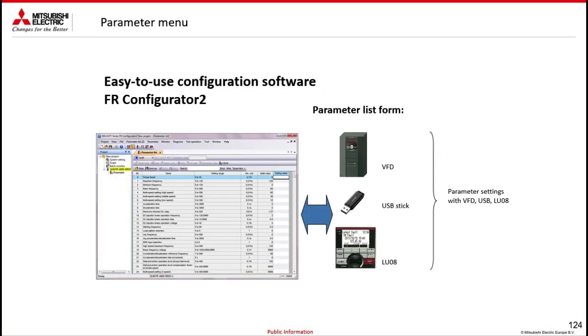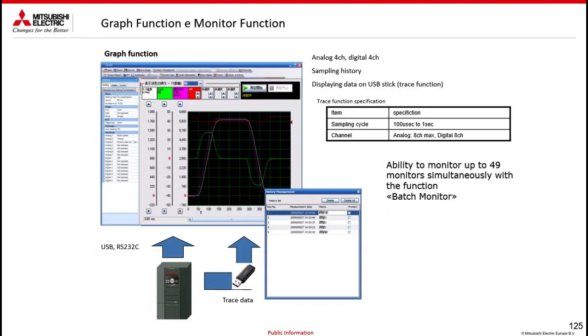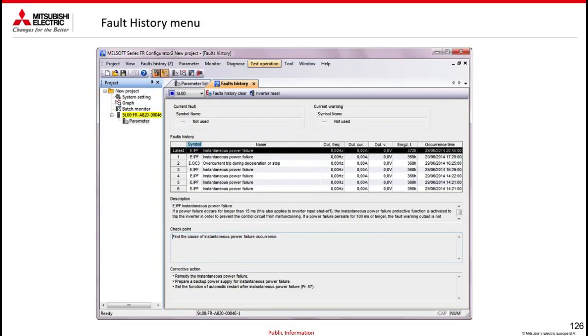You can configure the inverter directly from the software. You can read the parameters from the USB key, because maybe you went to a client who had an inverter, but you didn't have a computer while you had a USB key in your pocket. You read the parameters, you take them to the office, you plug them into a computer, and you can already pre-configure and do everything you need. You can also do graphics with the history, so you can edit the graphics. You can read the fault history, so all the alarms, such as the frequency, the current, what voltage came out, when it came out, how many hours after the power came on.